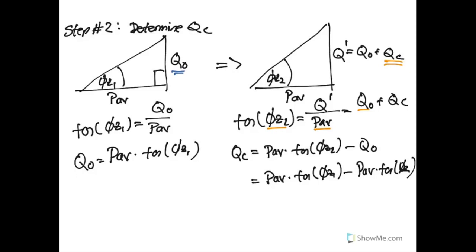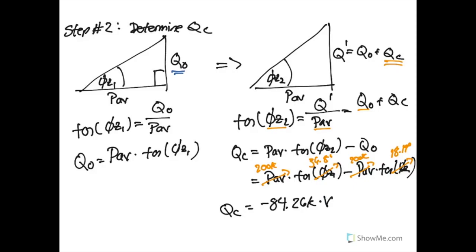For Qc, the original real power was 200 kilowatts, φZ1 was 36.8 degrees, and φZ2 was 18.19 degrees. Plugging in these values, we find that the reactive power due to the capacitor should be negative 84.26 kilovars.